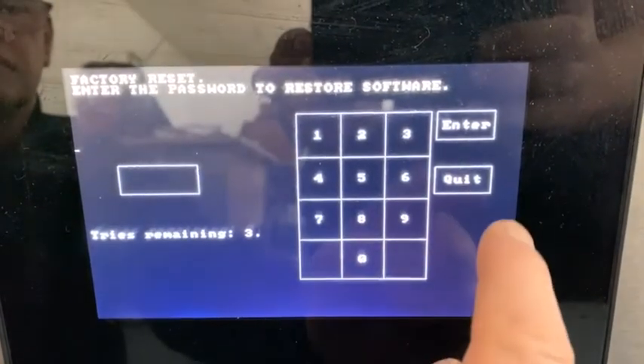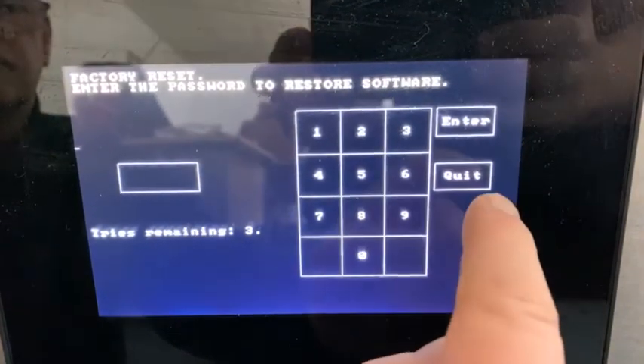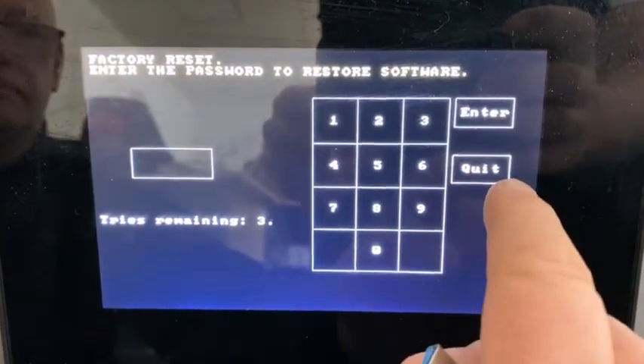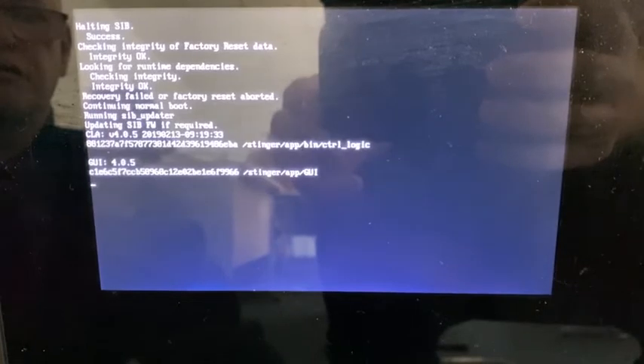You need to go back through the touchscreen calibration. When you get to this section, you need to remove the USB stick. Once you've taken that out, you can come back to the screen and press the quit button. This will now restart the controller and allow it to boot normally. If you don't remove the USB stick, it will continue to cycle with the next recovery, and you'll just completely redo what you've just done.